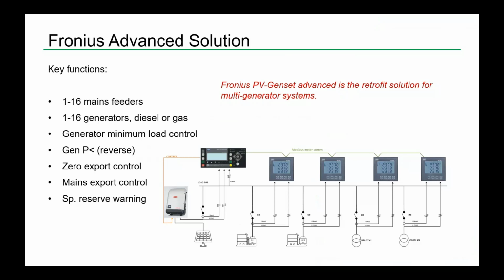If we move over to the actual solution, here's just one example that I've drawn. This is the Fronius advanced solution, the retrofit solution for multi-generator systems. I have shown in the picture 2 generators, 2 utility incomers, and there are limitations here: this is 16 mains feeders and 16 generators. These are the limitations when you use advanced.